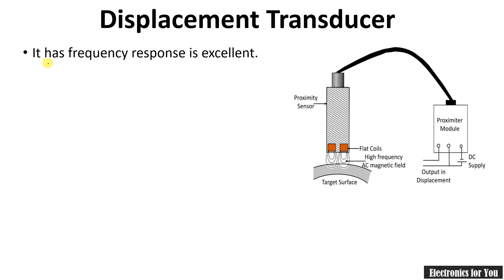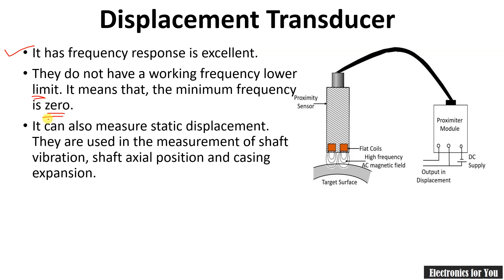The displacement transducer has an excellent frequency response and does not have a lower working frequency limit. It can work at a frequency of 0 hertz, meaning thermal expansion caused by temperature increment can be easily measured. It can also measure static displacement. They are used in the measurement of shaft vibration, shaft axial position, and casing expansion.